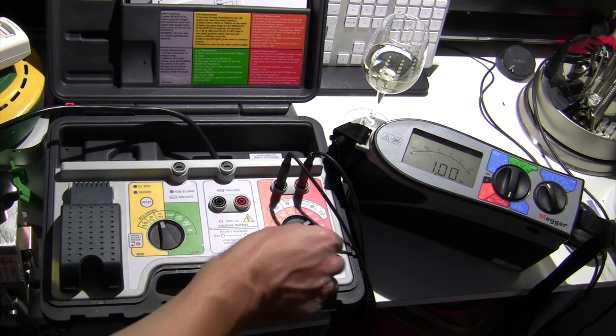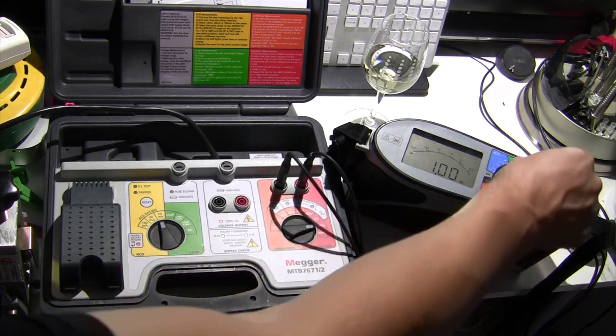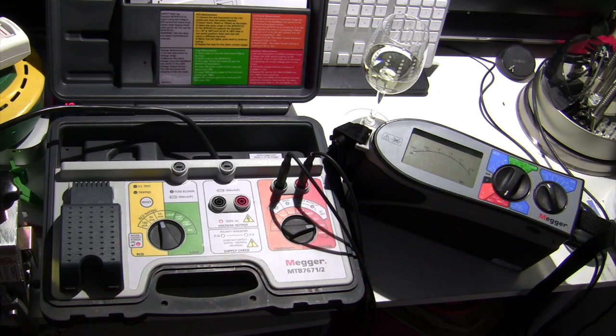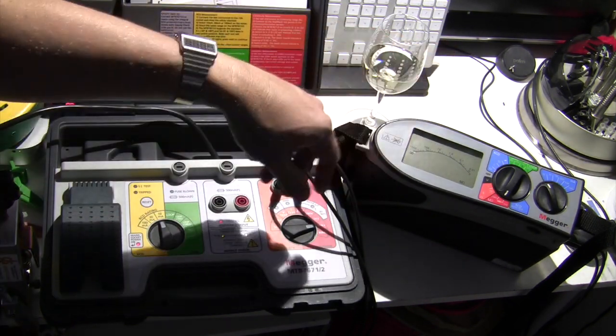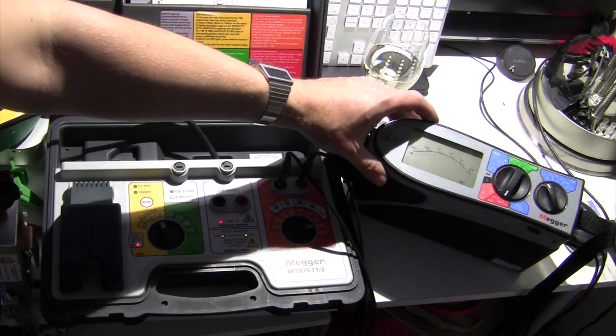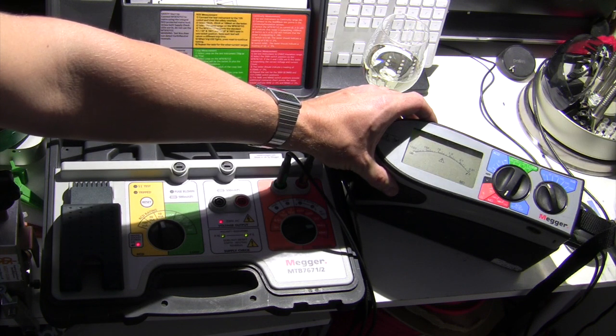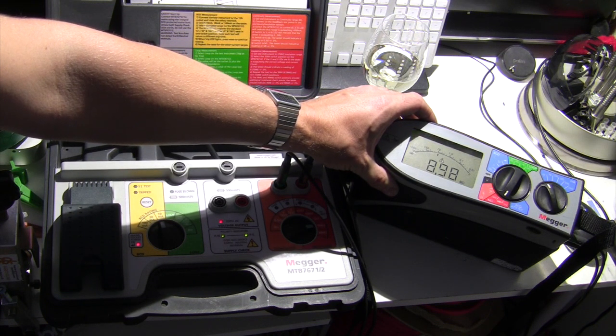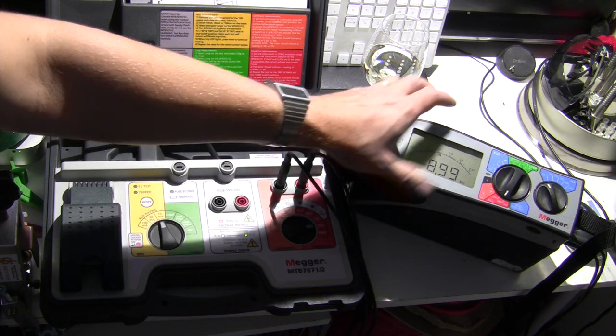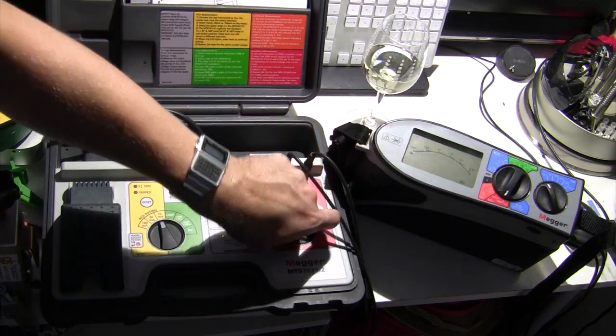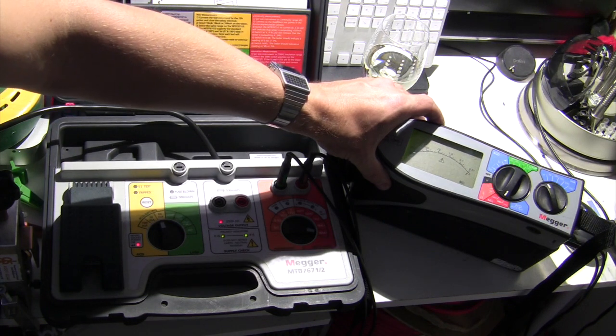Jolly good. Now we have two more tests that we can do here, and I'm just going to switch this back to 500 volts. Although the numbers that we get on here should be the same, regardless of whichever setting we use. This is the 9 megohm test, which should give us 9 megohms, and I'm turning the wrong dial. The 90 megohm test, which should give us 90 megohms.